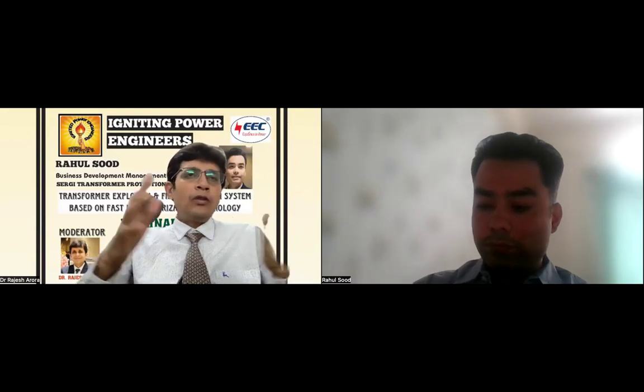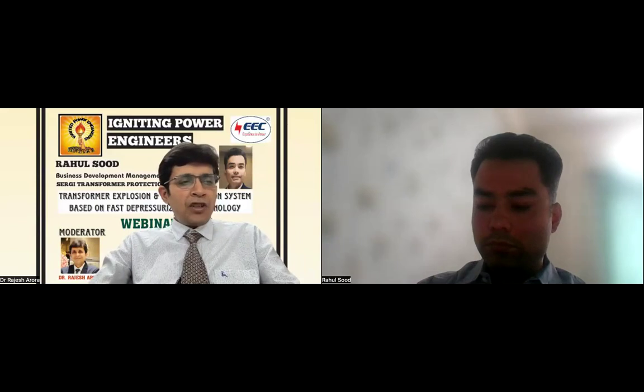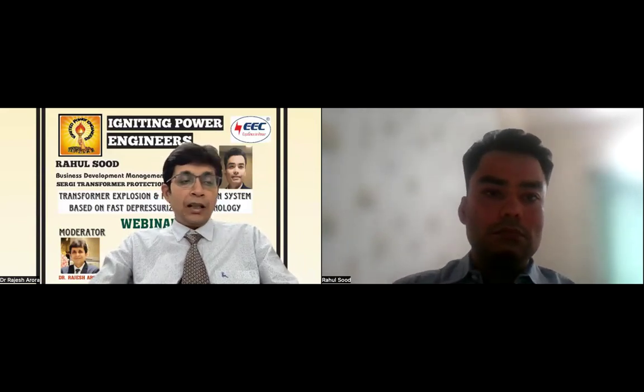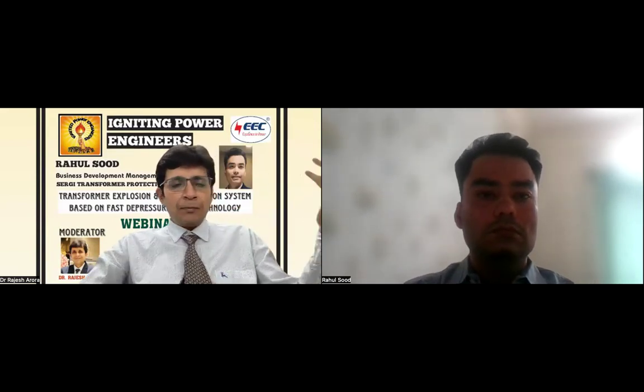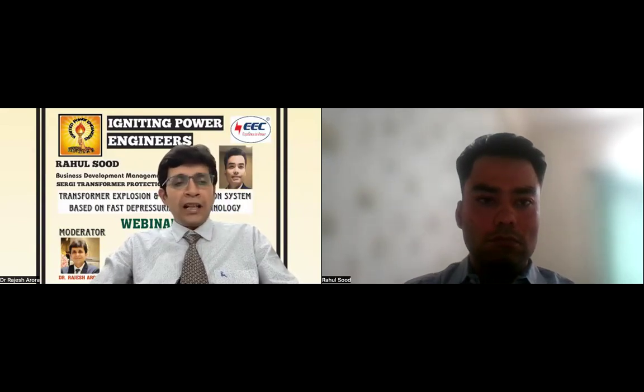If we talk about the reasons for all these failures, I have mentioned tap changer, bushing, core, winding, cooling system, and tank failure. As per the report, the contribution of each factor is: 50% because of winding insulation, 9% because of aging, 8% because of winding, and for reactors, 22% attributed to bushing failure.